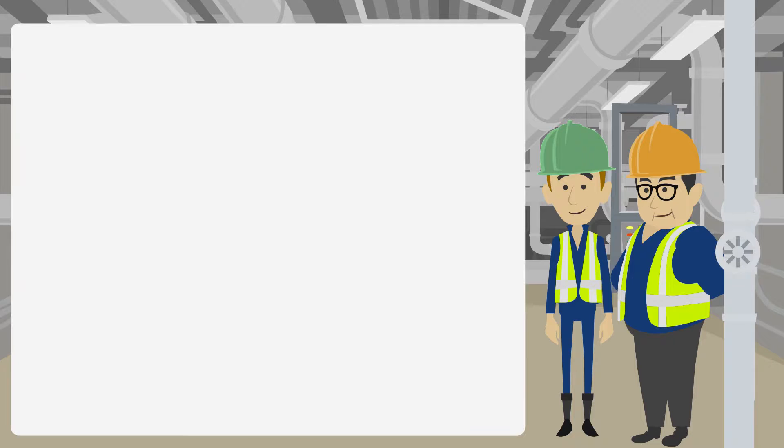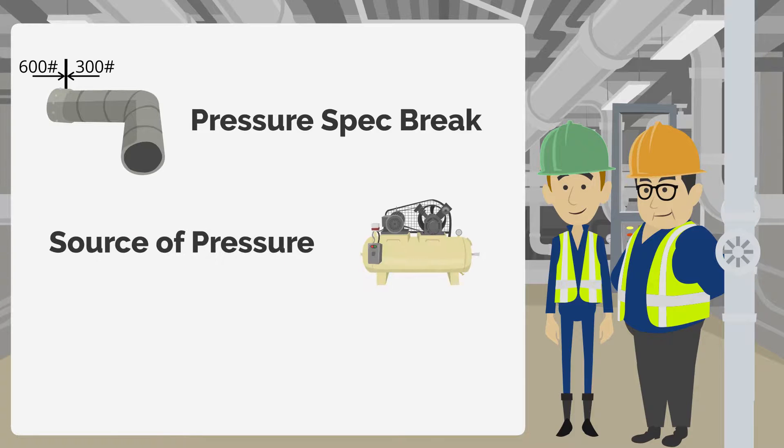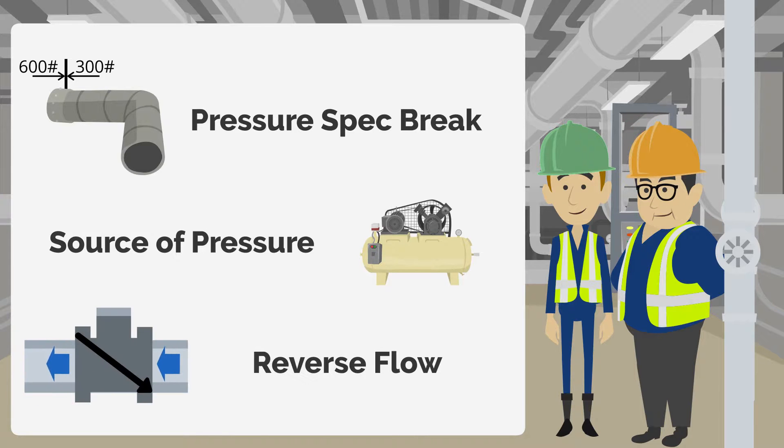Reverse flow overpressure is possible if the following are true. First, there is a high pressure to low pressure spec break. Next, there is a pressure source downstream of the spec break capable of producing pressures above the upstream rated limit. And finally, if flow and pressure are capable of traveling backwards, events like a pump being down or a flow path being blocked will stop driving flow in the forward direction.